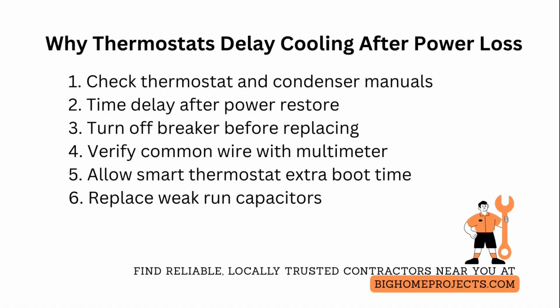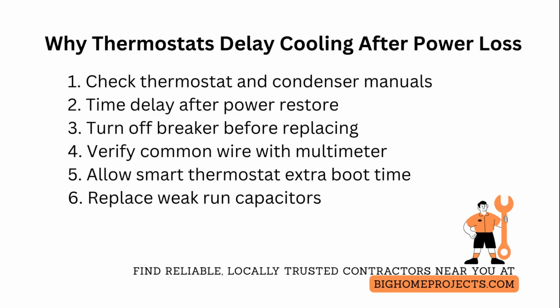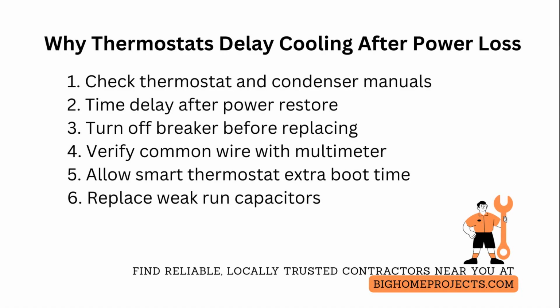If you want to confirm the exact delay, check the thermostat installation manual or the outdoor unit nameplate and firmware notes, and measure with a clock. Restore power, set cooling call, and time the interval to compressor contactor engagement at the condenser.